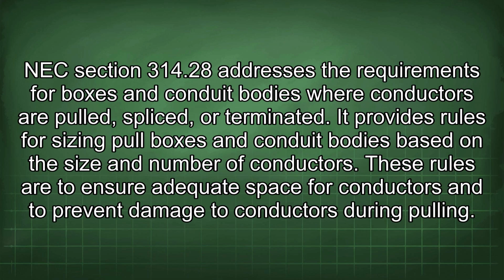NEC Section 314.28 addresses the requirements for boxes and conduit bodies where conductors are pulled, spliced, or terminated. It provides rules for sizing pull boxes and conduit bodies based on the size and number of conductors. These rules are to ensure adequate space for conductors and to prevent damage to conductors during pulling.